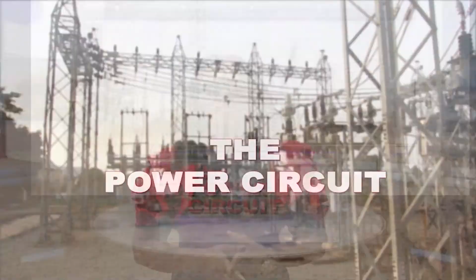Before we come to a close on this edition, may we remind you that you're not supposed to conduct any activity under these power transmission lines for your own safety. The Nigerian Electricity Regulatory Commission, NERC, safety regulation stipulates that for a 330 kV transmission line, a 50-meter distance split equally must be maintained on both sides of the lines before erecting structures, and for a 132 kV transmission line, you must maintain a 30-meter distance split on both sides of the line.